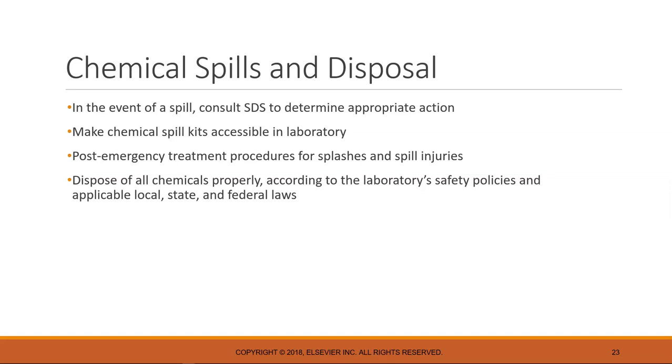If you are exposed, know the post-emergency treatment procedures for splashes and spill injuries. If it's in the eyes, you will immediately go to the eye wash station. If it's on your clothing, modesty goes out the window, especially if it's a very caustic material, and you remove clothing and go stand under the safety shower. How long do you have to do the eye wash or the safety shower? 15 minutes minimum, and somebody needs to be timing. A colleague needs to be timing for you.